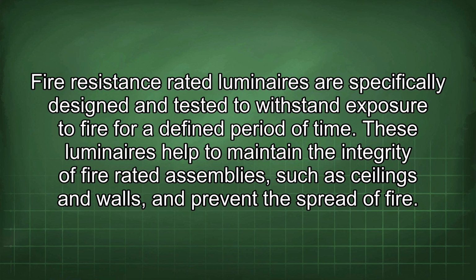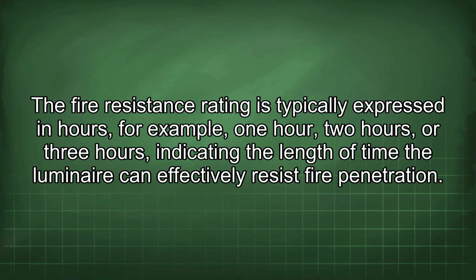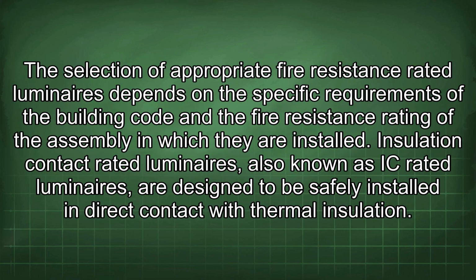These luminaires help to maintain the integrity of fire-rated assemblies, such as ceilings and walls, and prevent the spread of fire. The fire resistance rating is typically expressed in hours, for example, 1 hour, 2 hours, or 3 hours, indicating the length of time the luminaire can effectively resist fire penetration. The selection of appropriate fire resistance rated luminaires depends on the specific requirements of the building code and the fire resistance rating of the assembly in which they are installed.